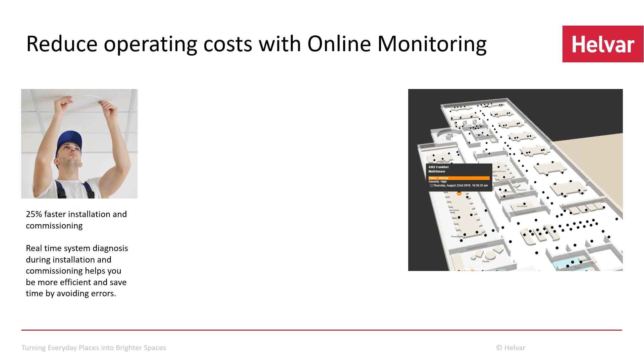He took his phone out, and on the phone he found an automated message from the Helvar system saying that he's using too much current in this subnetwork. He looked up and realized, yes, that's actually true, I put in too many devices. He was able to make that correction immediately, instead of having to realize it afterwards and come back to make changes. So the system allowed them to avoid mistakes during the installation and commissioning phase, and the feedback was that they completed the whole project 25% faster than budgeted. So very concrete savings and efficiency.